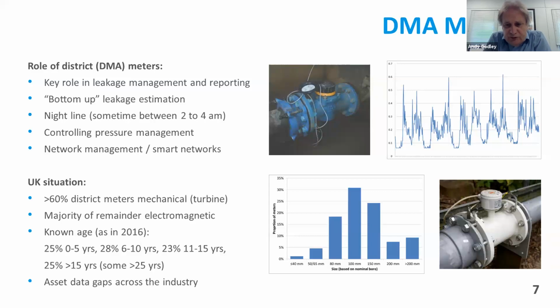There is a move across to electromagnetic meters, as on the bottom right, particularly in terms of the benefits they offer from the stability of performance over the longer term. And probably in common with most areas, our district meters are typically around 100 millimeters in size, so 80, 100, 150 are the most common sizes. A few small ones and a few larger ones. Larger ones, particularly where we have cascaded DMAs. So that's where one DMA is feeding another DMA.